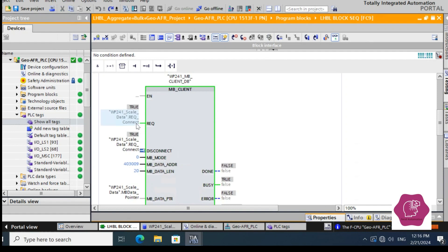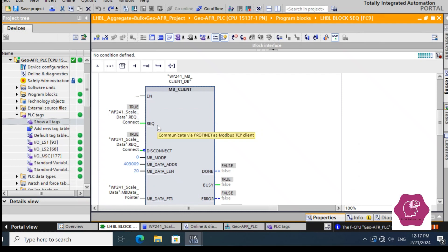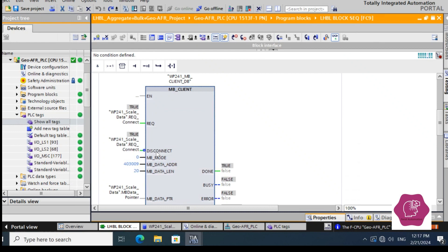Here we have the connect request — 'request_connect' bit. This is a boolean tag required to request communication or request data from the Modbus server. You can give a pulse or keep it always on — no problem. If your communication is read-only, you can keep it always on. For reading, you have to set MB_MODE as 0. For writing, you set MB_MODE as 1. And you have to set 0 for connection establishment; if you give only 1 (true), communication will not be established.